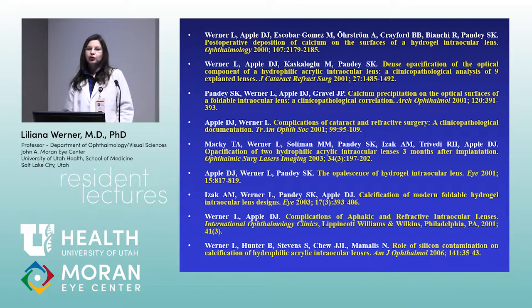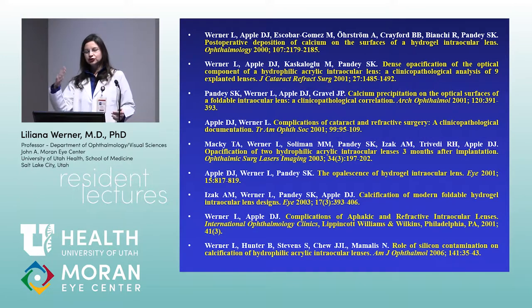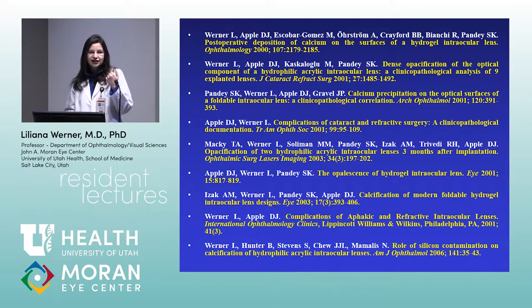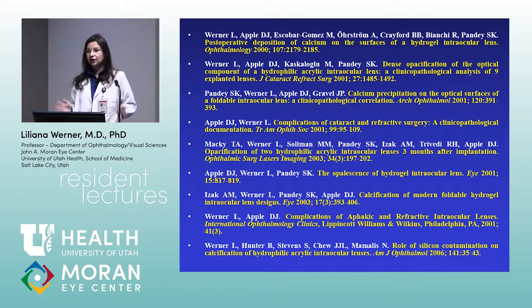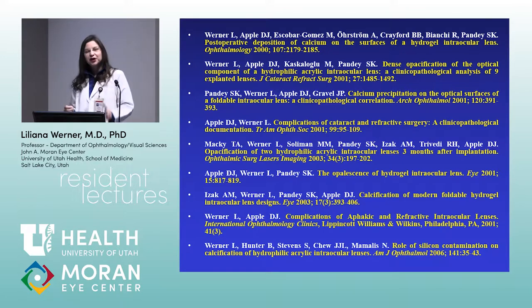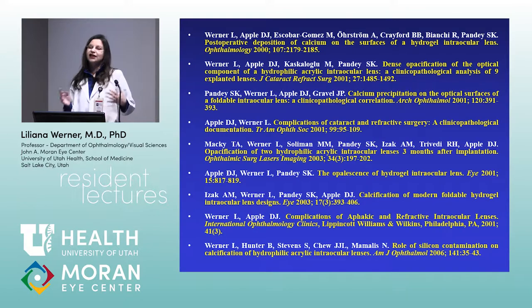The most important problem with hydrophilic acrylic lenses is calcification. If a patient comes with decreased vision after cataract surgery, the posterior capsule is clear or already YAG'd, and you see haze at the slit lamp in a hydrophilic acrylic lens — calcification must be your first thought. Major designs that experienced calcification include the Hydroview by Bausch and Lomb, which was available in the United States, and two others manufactured in the US and exported. The Hydroflex had granularity covering the lens surface; others had calcification within the substance.